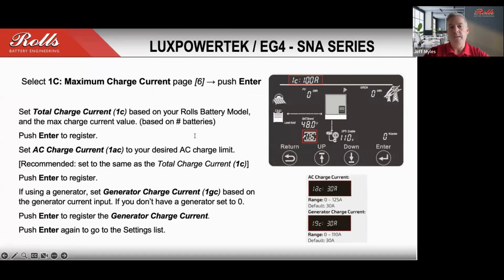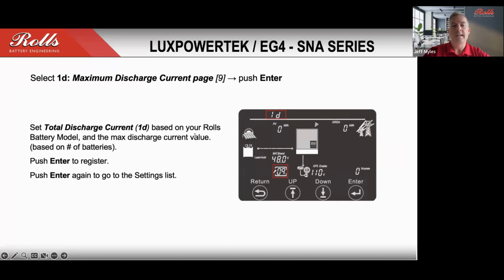So again, walking through those steps, setting up the inverter protocol, making some tweaking on the settings based on the particular install. Certainly, that's going to happen with most installations. So these are going to provide you general guidelines to ensure that it's going to be properly charging and discharging, and within the conditions of the BMS. And then, again, if there are any particular settings outside of those, then those settings would not be included in this installation guide. One thing, again, whether you're working with the LXP or the SNA series, is it's very important that you set those current limits in the unit to ensure that it's not going to trigger the BMS to shut down because of overcurrent, especially if you're running less than 5 units in the stack.